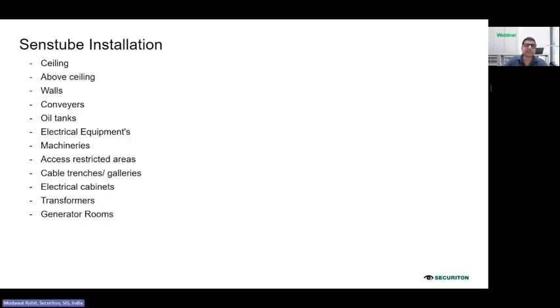The sensing tube can be installed on ceilings, above ceilings, walls, conveyors, oil tanks, electrical equipment, machinery, and access restricted areas like lift shafts. Then you have cable trenches, galleries, electrical cabinets, transformers, and generator rooms. I would like to bring to your kind notice that this system is not only used as a heat detection system. It can be used as an equipment monitoring system as well. If you want to monitor equipment, you can run these tubes in whichever way you would like.